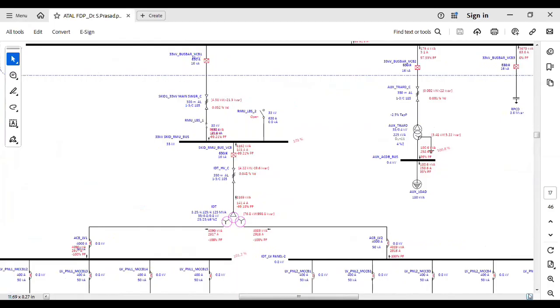And therefore, we are conducting load flow analysis using different softwares. According to the CEA regulations also, for each analysis, the softwares to be used need to be approved. So you can conduct the test using PSSE software, or you can conduct the test using ETAP software. Based upon the grid code of different countries, you have to use those softwares to conduct the analysis. Otherwise, it will not get accepted.